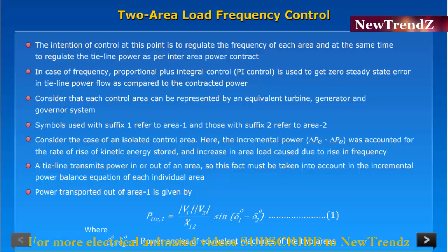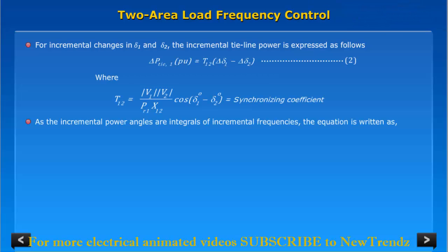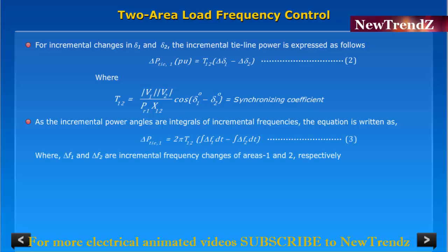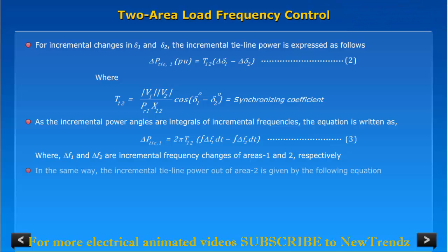For incremental changes in Delta one and Delta two, the incremental tie line power is expressed as follows. Since the incremental power angles are integrals of incremental frequencies, the equation is written in terms of Delta f1 and Delta f2, which are the incremental frequency changes of areas one and two respectively. In the same way, the incremental tie line power out of area two is given by the corresponding equation.